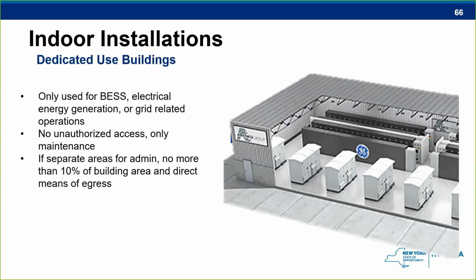This is an example of what a cutaway of a dedicated use building might look like. And again, these buildings are used for the sole purpose of housing an energy storage system. You can have admin personnel in there, but that area is only limited to 10% of the floor space, and they have to be blocked off by firewalls and have their own exits. And again, a non-dedicated use building would be anything that doesn't meet the specifications outlined here. And as you can imagine, the requirements for those two types of buildings differ.